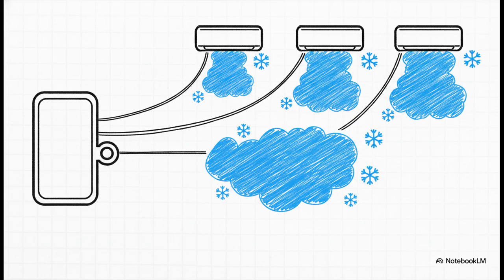Now, when you're actually laying out the space, you get some really cool grouping options. The hybrid branch controller lets you connect up to 3 fan coils together on a single port. But there is a catch. All of those grouped zones must share a similar thermal profile. Because there's only one set of pipes carrying either hot or cold water out of that single port, all the connected zones have to operate in the exact same heating or cooling mode at the same time.